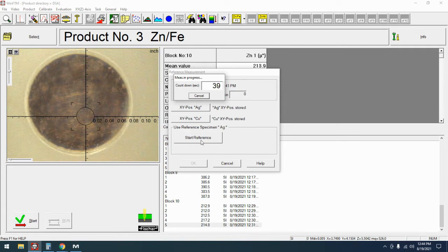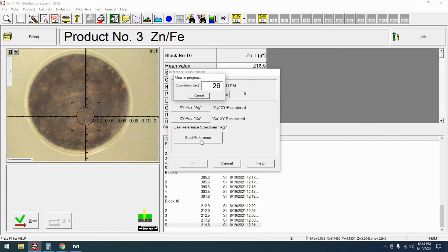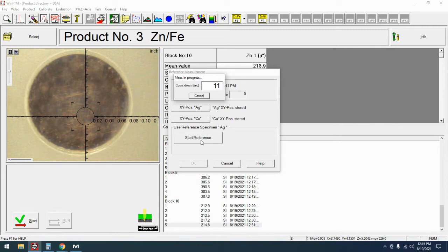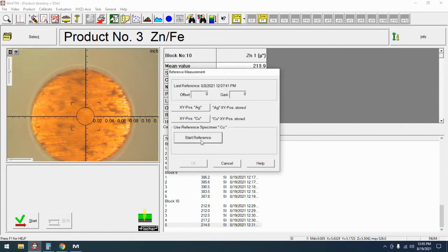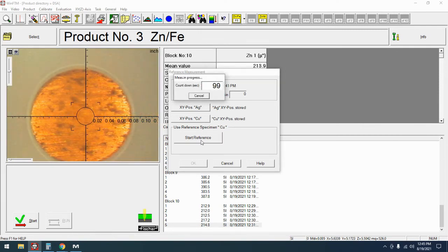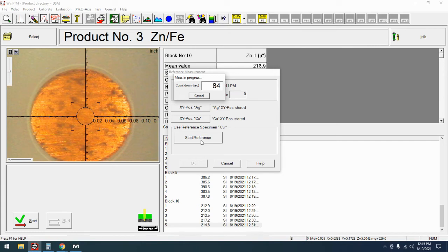Don't be surprised if sometimes you get through silver and it restarts counting and does a series of short four second measurements. Just means that for whatever reason your spectrum needed a little bit more of a shift than the software was initially expecting and that's okay. Now I finished with the silver and you can see it just zipped on over to copper.